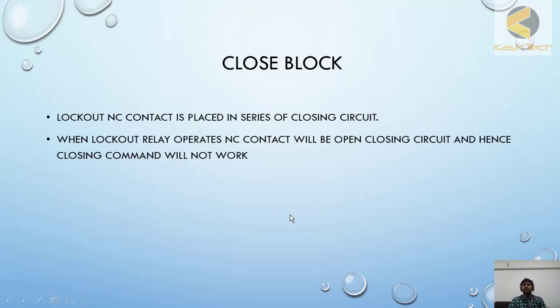Lockout normally closed contact is provided in the closing path in series. So when the lockout is operated, NC contact will become open and it will cut the DC supply of closing circuit.